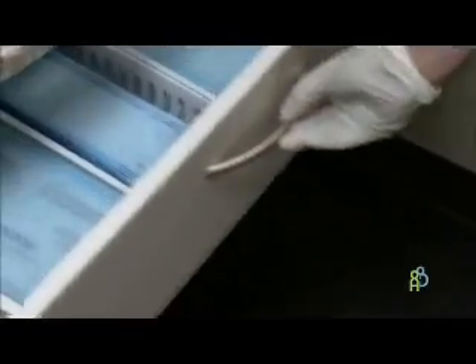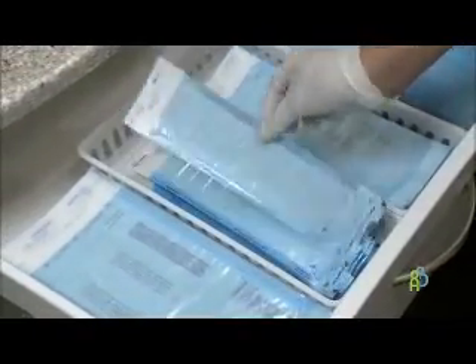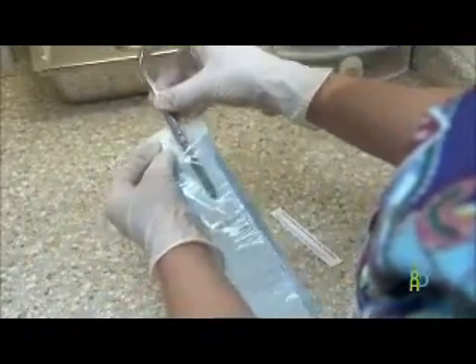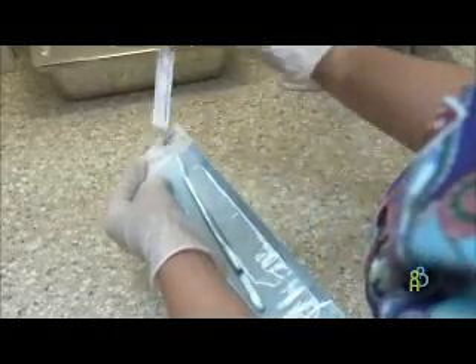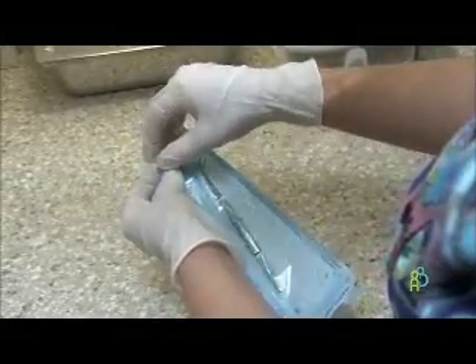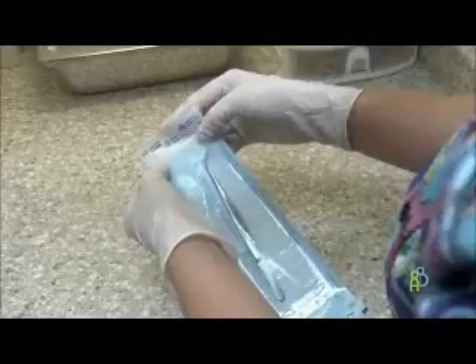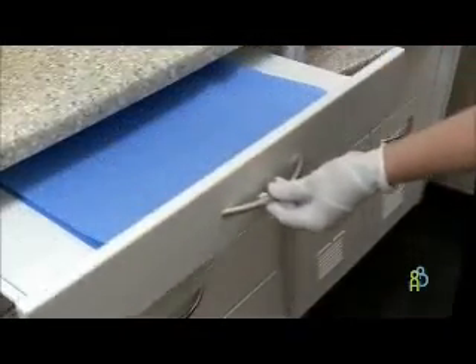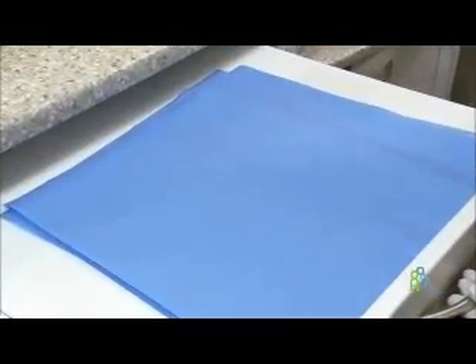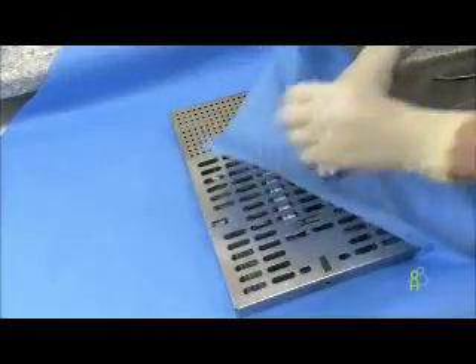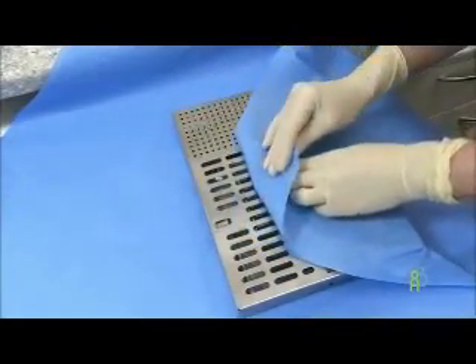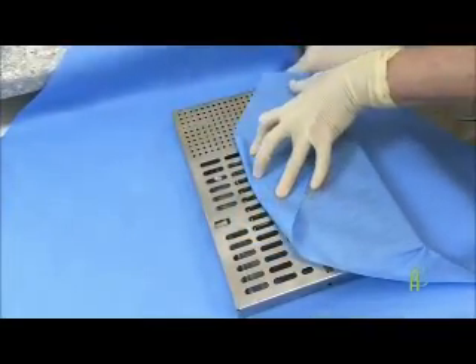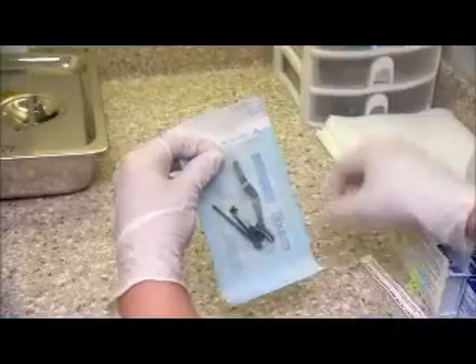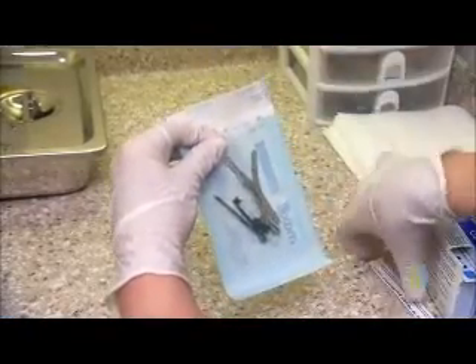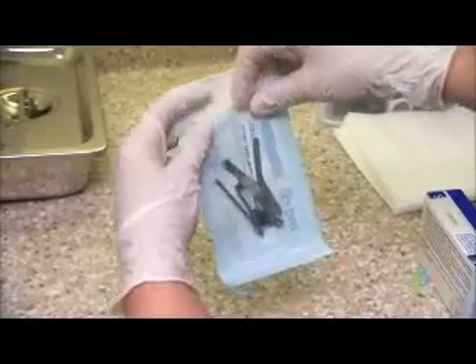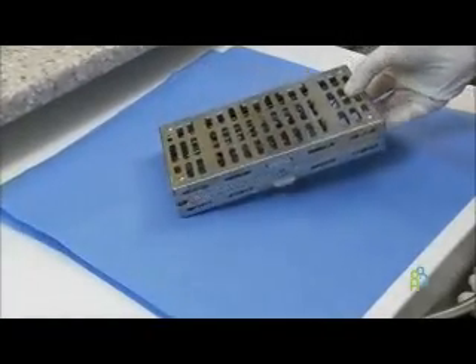The next step in reprocessing is the wrapping or packaging of clean and dry devices prior to sterilization. This task should be completed in the clean section of the reprocessing area. Wrapping materials must be stored in a place that is protected from contamination. The type of wrap chosen will be influenced by the manufacturer's instructions for both the wrap and instruments. Dental devices can be wrapped in either single-use paper plastic peel pouches or single-use non-woven wrap.